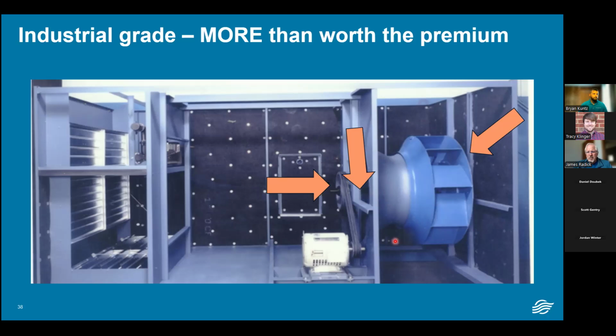The center arrow is pointing to the inside that we manufacture. We take a fan cone and a fan wheel that's purchased from a supplier, and we build our own housing around it. That allows us to optimize the amount of CFM that we can put through a given cabinet size. It allows us to make sure that it's built strong and robust.